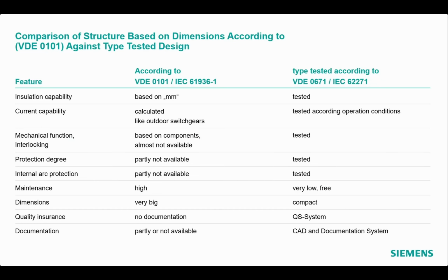In earlier times, in general, the design of switchgear was more component-oriented. In order to ensure certain dielectric strength, a minimum distance must be maintained for insulation capability as per VDE 0101 standards.